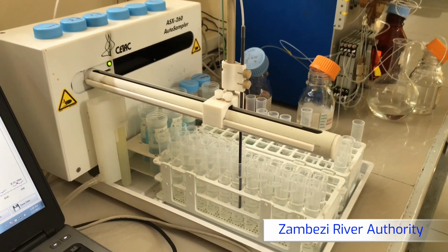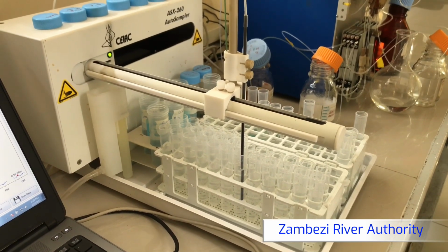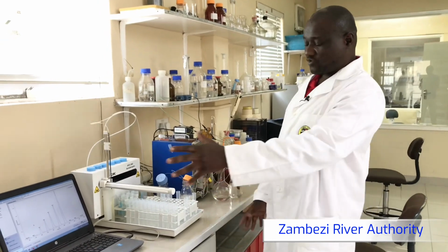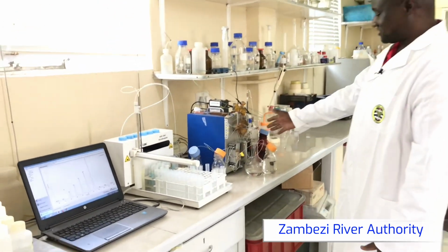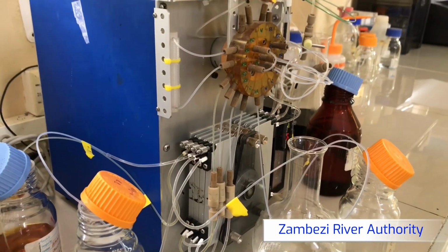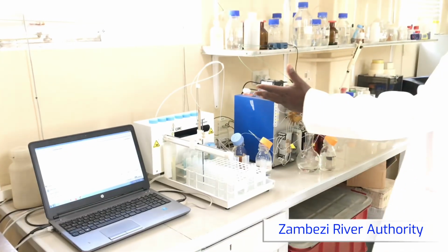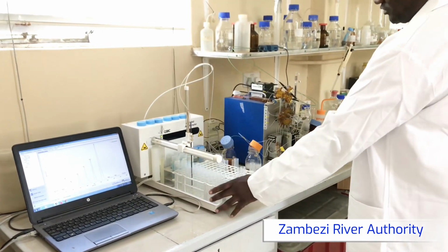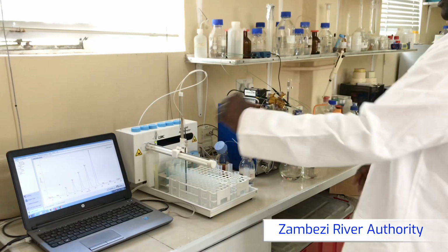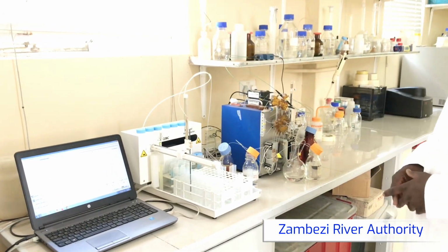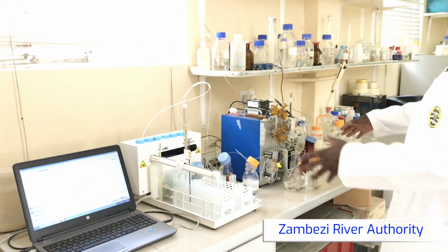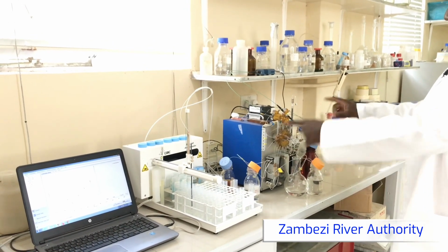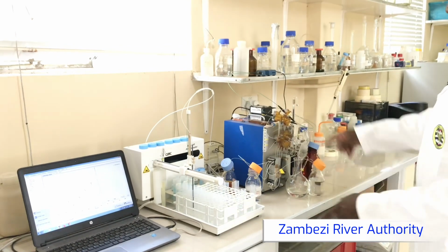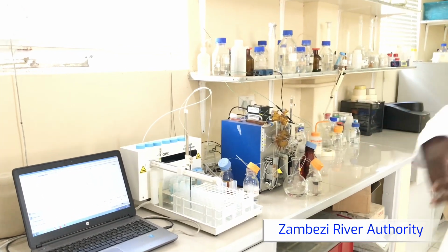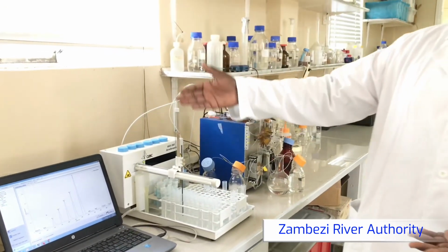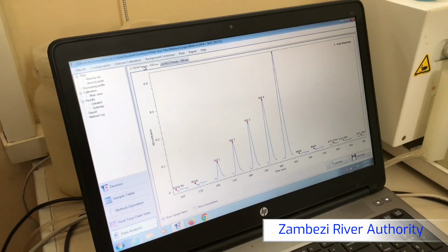So we've got about 30 samples. As you can see, there's an auto sampler here connected to a computer, as well as this unit, which is basically the main unit. So what it does is you put your samples in the auto sampler. Of course, you ID them using the program on the computer. Then we've got a pump here and the reagents. So the pump pumps the reagents, mixing them with the sample, and then the reaction takes place. So what you see here on the screen are the results that we are getting from the samples that are undergoing processing.